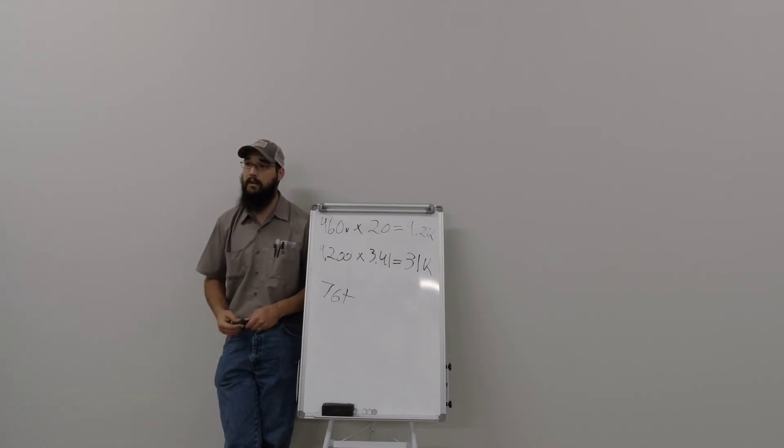Just because it's 70 degrees coming in doesn't mean that coil doesn't have a lot of load on it. Because it may be 70 degrees coming in and it may be say 45% on the fan, which is pretty standard. But yet your condenser is still running fairly high, right? Your condenser saturations are higher than normal. Your building water temp is higher than normal. Well, maybe because it's 85% humidity outside and the buildings struggling to stay below 60%. Those are all factors we have to take into account.